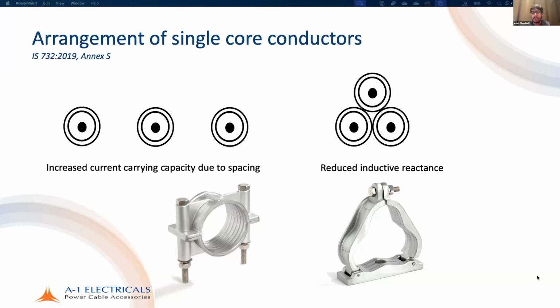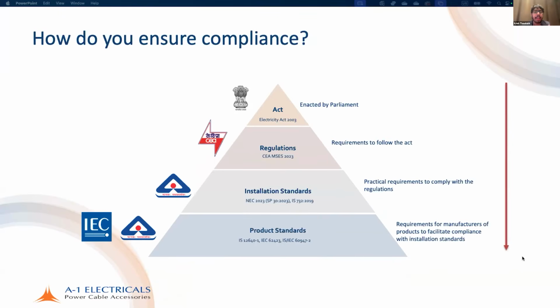Now, okay, this is technical information for you, but crucially, how do you, as an electrical designer, as a consultant, as an installer, ensure compliance? Remember, the regulatory framework in India starts from the Act and ends at product standards. The first thing is selecting a product that meets the requirements of the product standard. That is extremely important. If you don't do this, you are not complying with the installation standard, you are not complying with the regulation, and you're not complying with the Act, right? So that is a simple case of non-compliance, and we know that not selecting a product according to the product standard is punishable according to the Act.